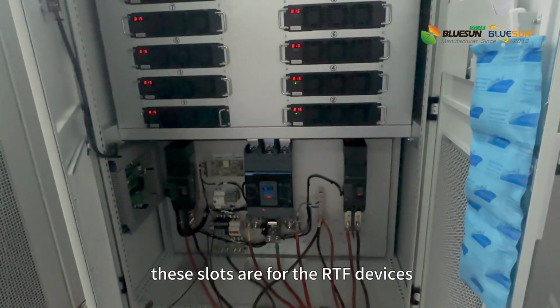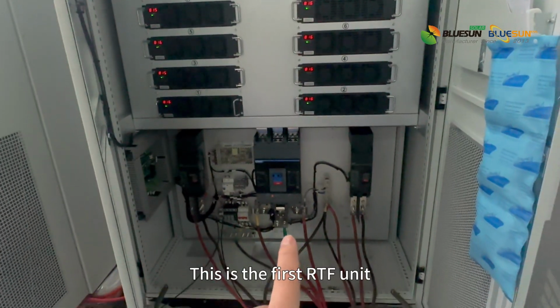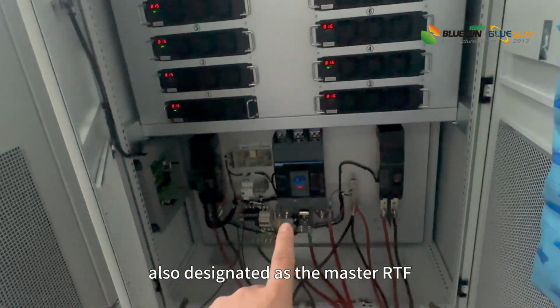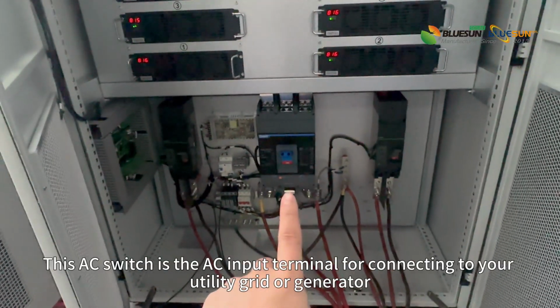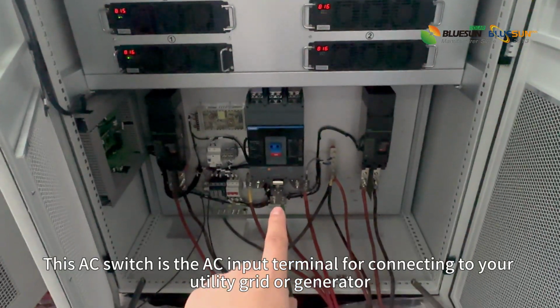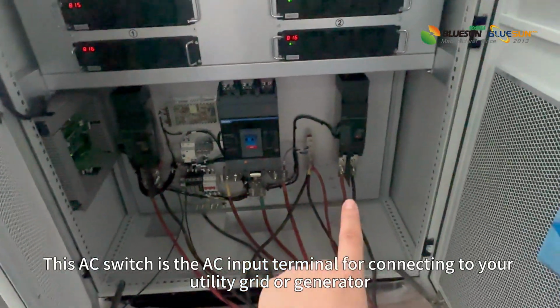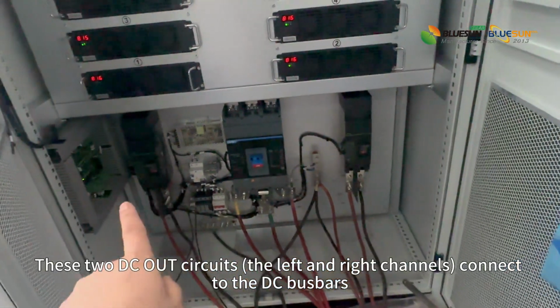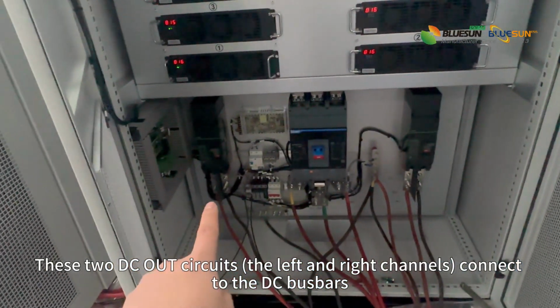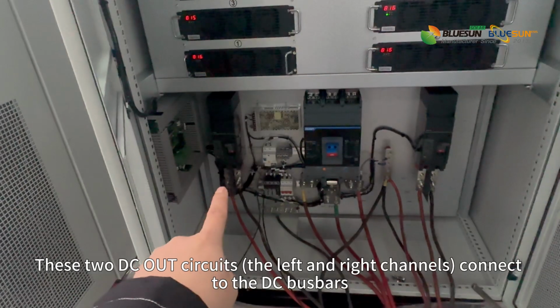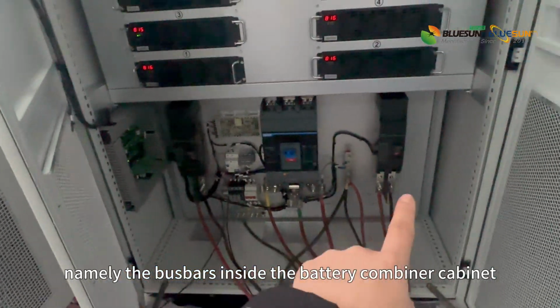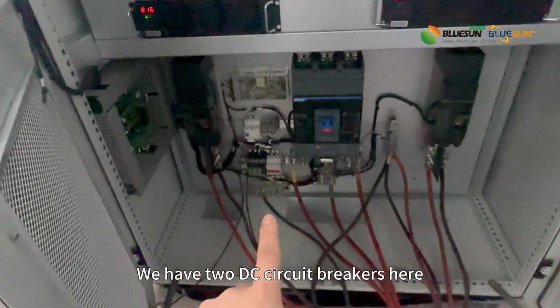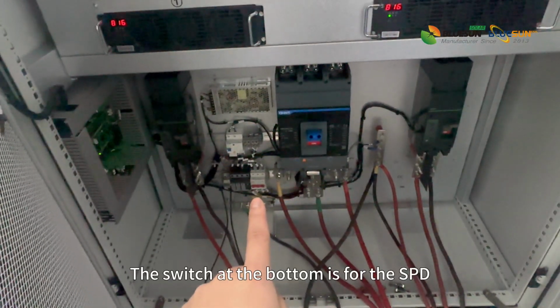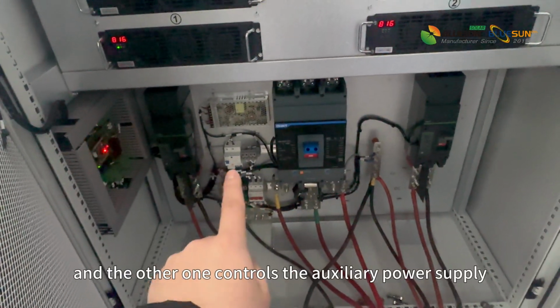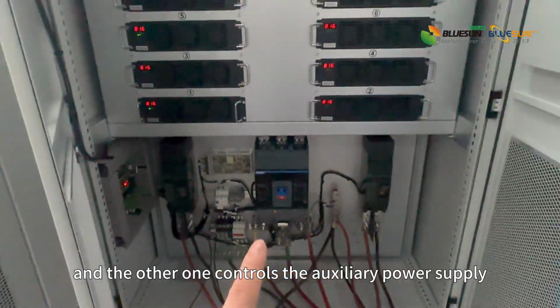These slots are for the RTF devices. This is the first RTF unit, also designated as the master RTF. This AC switch is the AC input terminal for connecting to your utility grid or generator. These 2 DC out circuits, the left and right channels, connect to the DC bus bars, namely the bus bars inside the battery combiner cabinet. We have 2 DC circuit breakers here. The switch at the bottom is for the SPD, and the other one controls the auxiliary power supply.